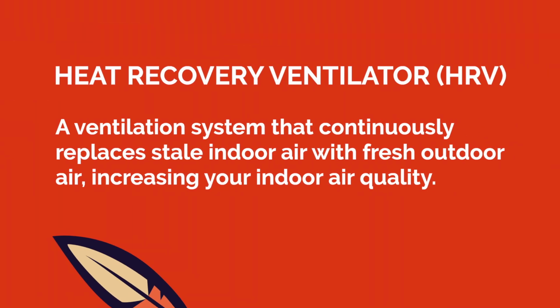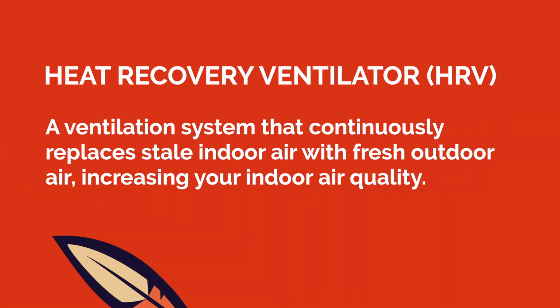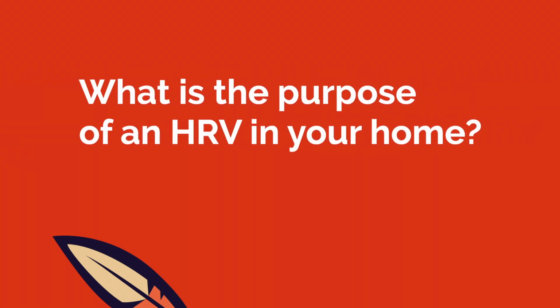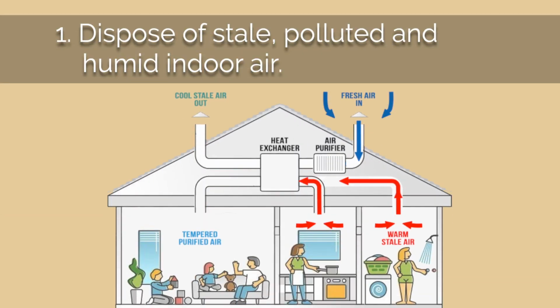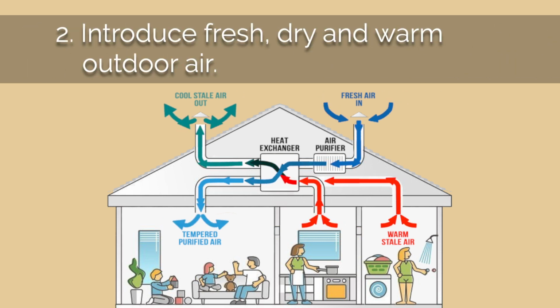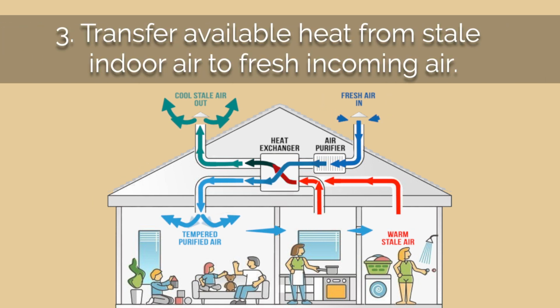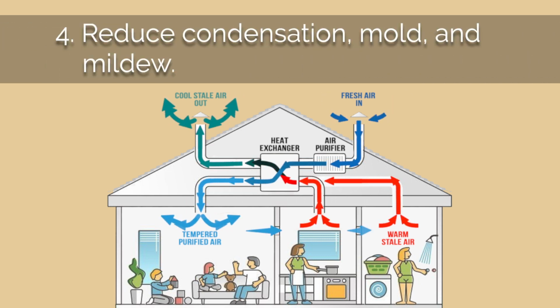A heat recovery ventilator, or HRV, is a ventilation system that continuously replaces stale indoor air with fresh outdoor air, increasing your indoor air quality. So what is the purpose of an HRV in your home? Number 1, dispose of stale, polluted, and humid indoor air. Number 2, introduce fresh, dry, and warm outdoor air. Number 3, transfer available heat from stale indoor air to fresh incoming air. Number 4, reduce condensation, mold, and mildew.